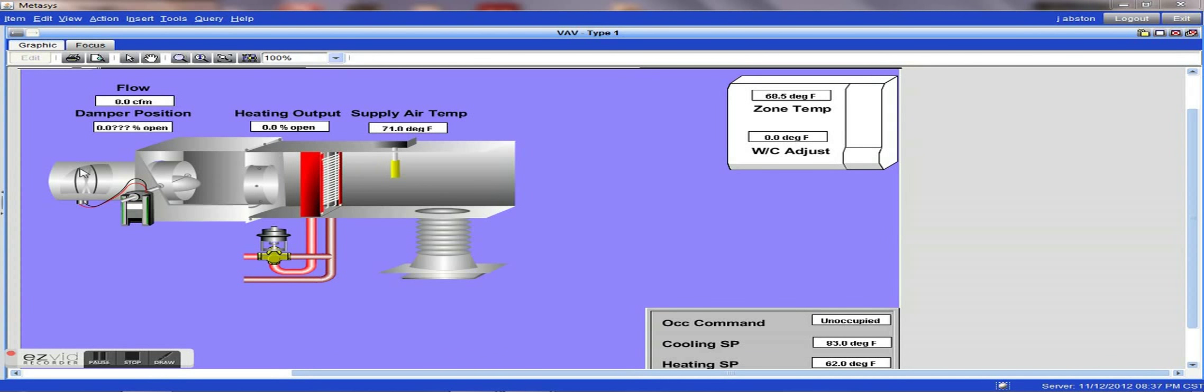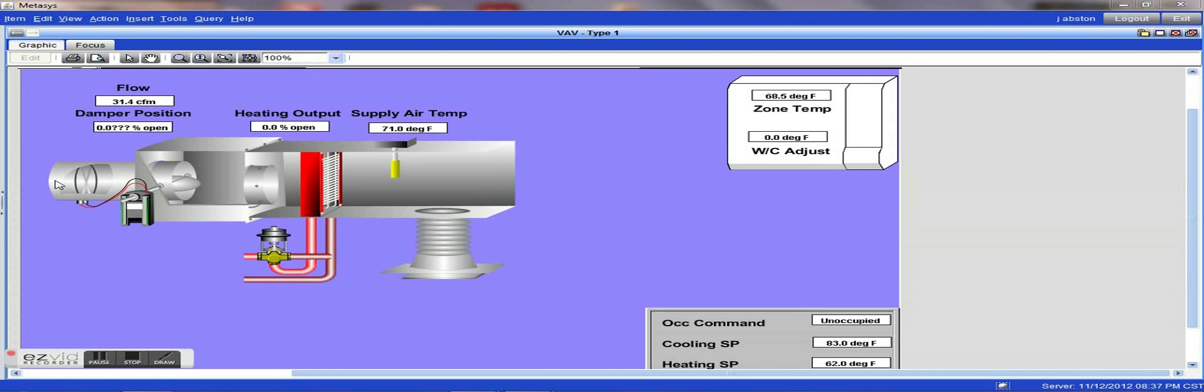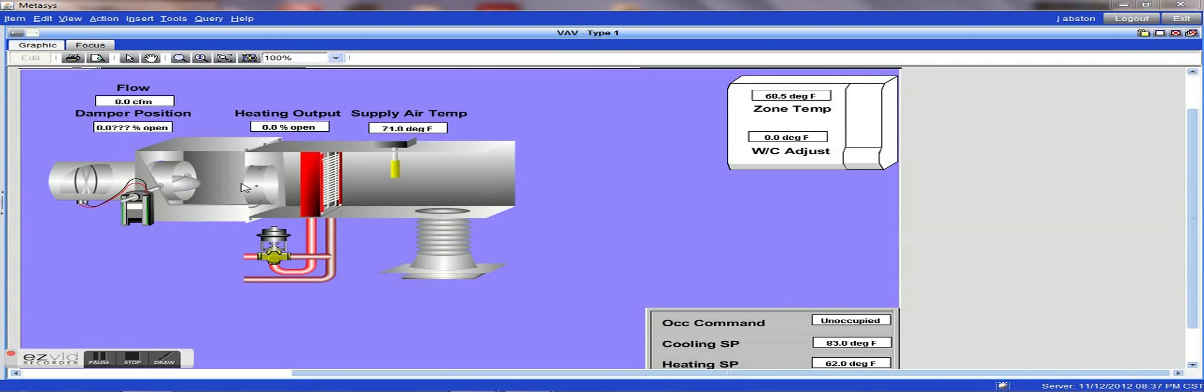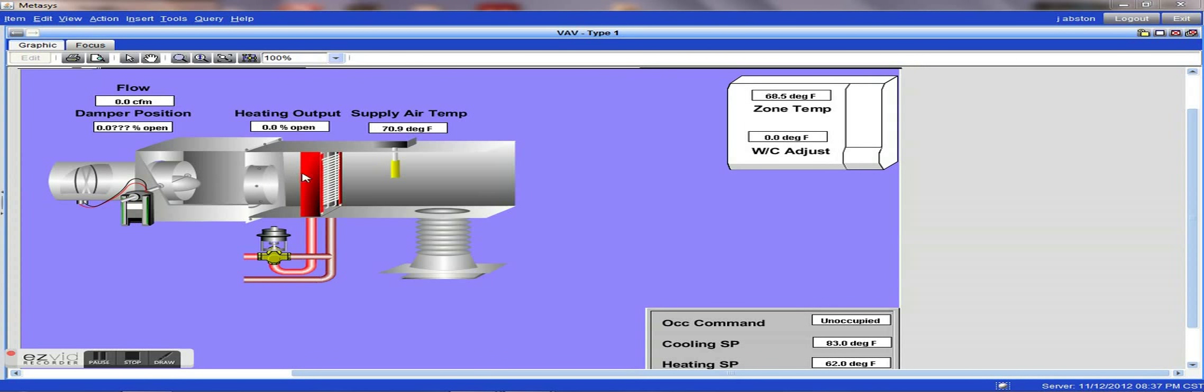By raising the discharge temperature from say 55 degrees to 62 degrees on a cold day, you can still allow, if any of the spaces get warm, you still have adequate cool enough air to cool those spaces. However, by raising that discharge temp from your air handler, it will help to increase the temperatures in your space a little more rapidly.